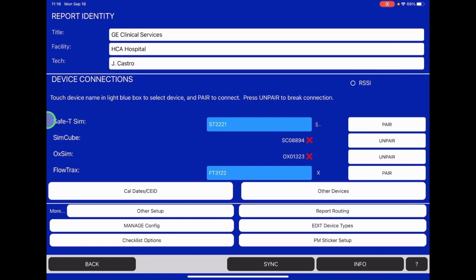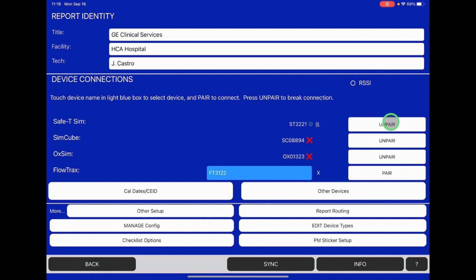Locate the device you're connecting. In this case, we're going to be connecting the Safe-T Sim. You tap on this field here, it'll open up a window for you to locate any Mobilize devices available to pair to. The ID of the device equals the serial number. You select it, and then you hit pair, and it will connect that safety analyzer to your Mobilize app so that you can control it and perform all of the testing necessary.